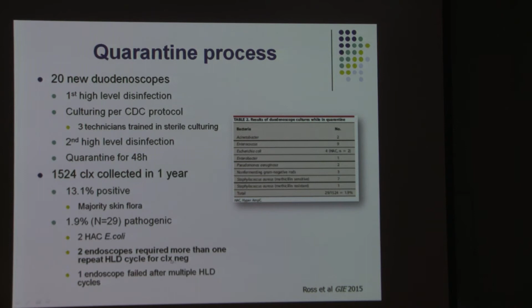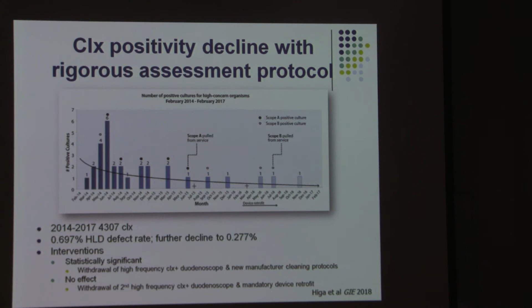Now, recently, the same group published their follow-up study for an additional 3 years after the outbreak, where they had more than 4,000 cultures. Since they instituted that very rigorous assessment protocol, they were able to bring their high-level disinfection failure rate from, as you remember, almost 2% down to less than 0.27%. For them, the statistically significant intervention was withdrawal of one of the endoscopes that had a high frequency of culture positivity, and they were following new manufacturer cleaning protocols. Interestingly, withdrawal of a second endoscope, also with high culture positivity, as well as mandatory device retrofit, did not result in changes.